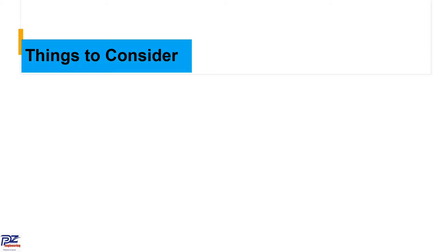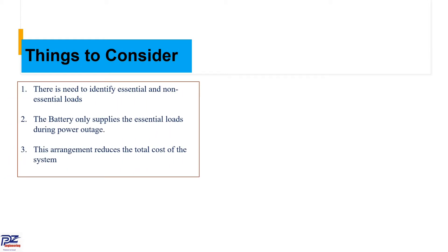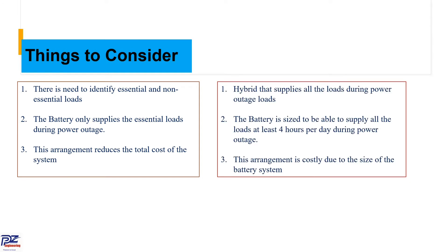Things to consider when designing our AC coupled system: there is a need to identify the essential and non-essential loads. The battery only supplies the essential loads during a power outage, and this arrangement reduces the total cost of the system. The second arrangement is where the battery supplies all the loads during a power outage. The battery is sized to supply all the load for at least four hours per day during the power outage.